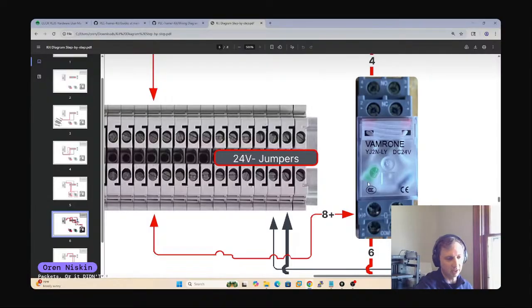So this is the relay coil. This is the relay coil connections. And then the rest of these screws are the contacts. Sorry, the relay contacts. So when the relay energizes, the normally closed contacts open and normally open contacts close. In de-energized, the normally open contacts are open, normally closed contacts are closed. And then this is common. So this is where the other side of the switch goes. So always two wires go into a switch. One side is up here, one side is down here.